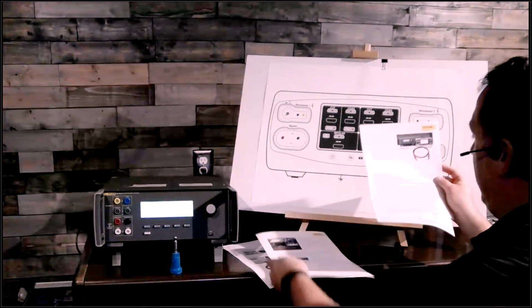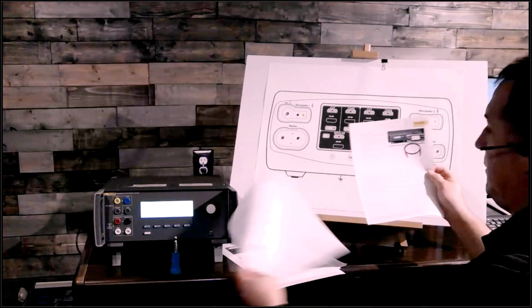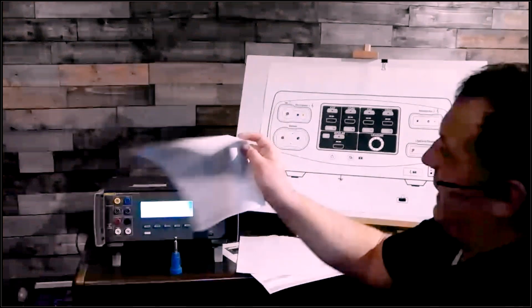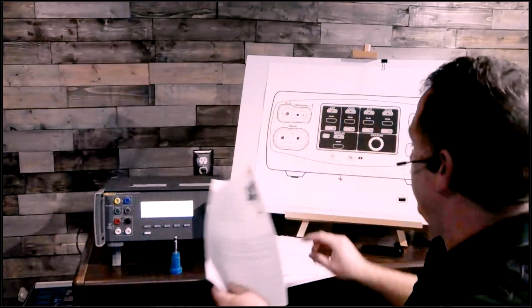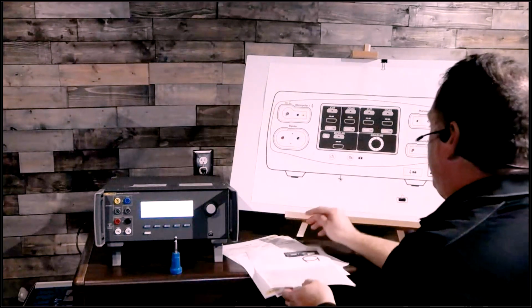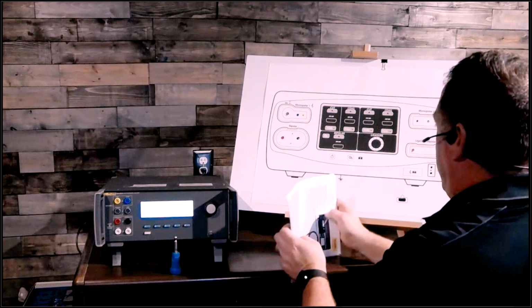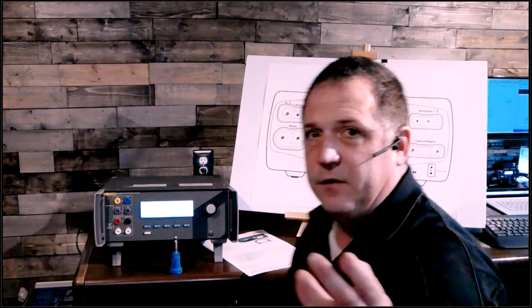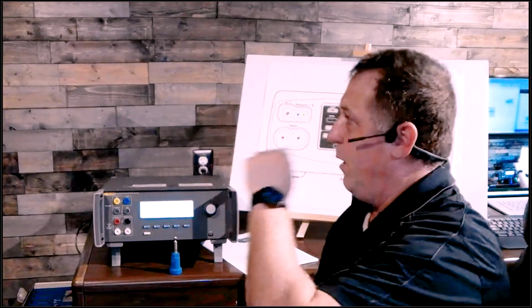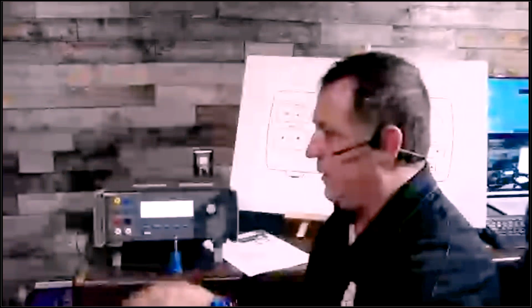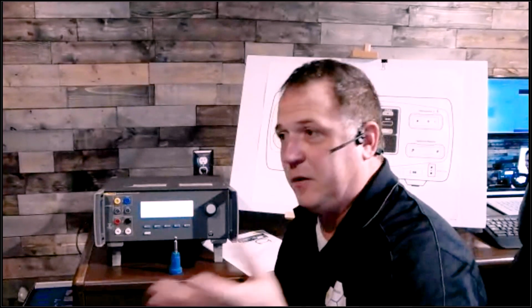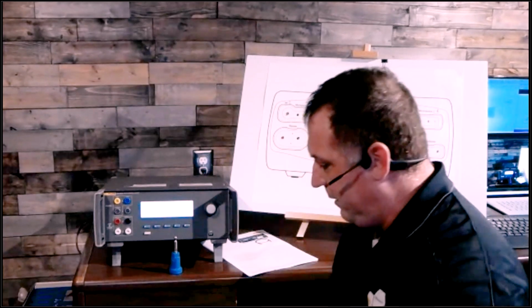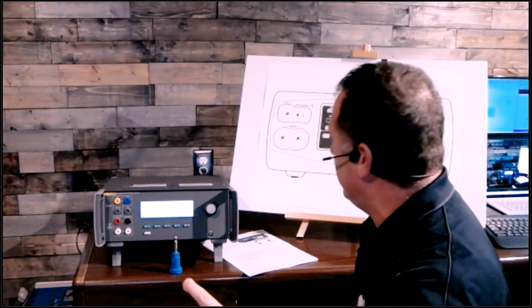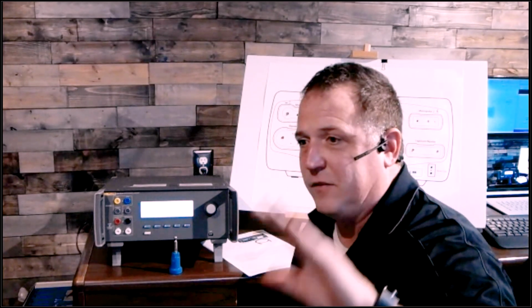So on this page, when we talked about leakage from the top, down here at the bottom is high frequency leakage. When we're testing for normal electrical safety, we're testing for 60 hertz energy — that's what all the wall outlets in the United States produce. Overseas, other countries, you might hear 50 hertz. I think there's still one city in the United States that uses 50 hertz, but only one — that's a bonus question if you know where it's at. So we're testing at 60 hertz.